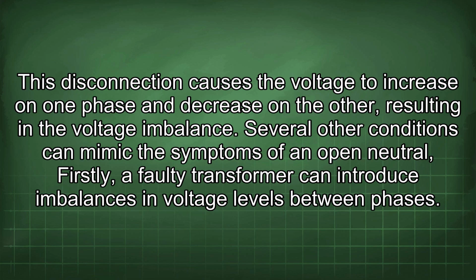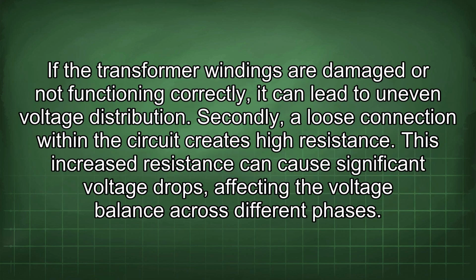Several other conditions can mimic the symptoms of an open neutral. Firstly, a faulty transformer can introduce imbalances in voltage levels between phases. If the transformer windings are damaged or not functioning correctly, it can lead to uneven voltage distribution. Secondly, a loose connection within the circuit creates high resistance. This increased resistance can cause significant voltage drops, affecting the voltage balance across different phases.